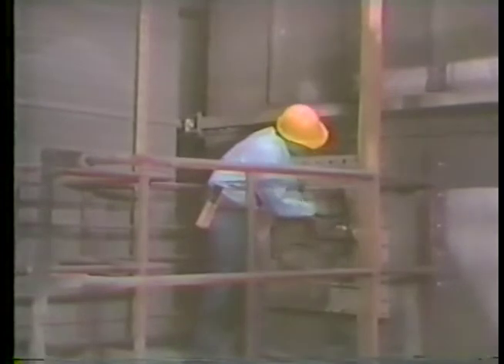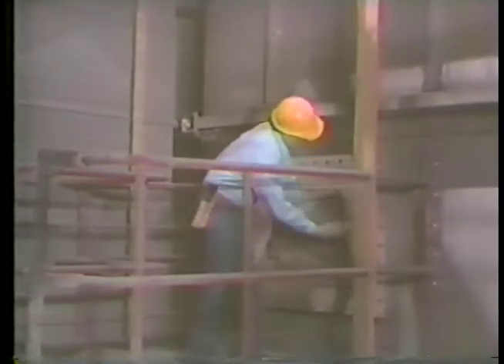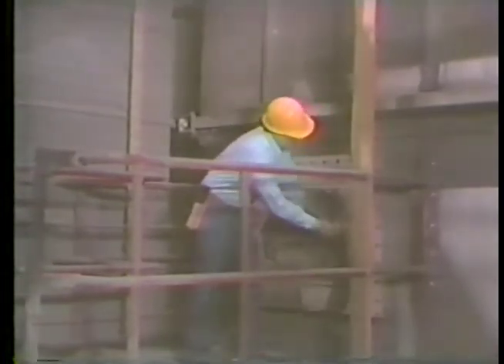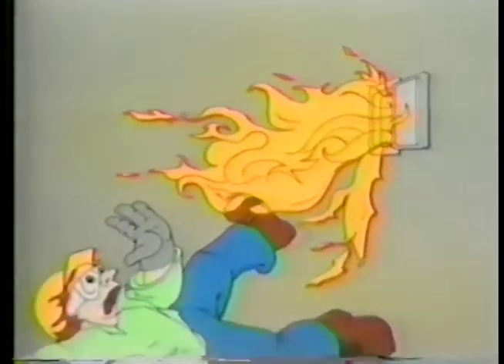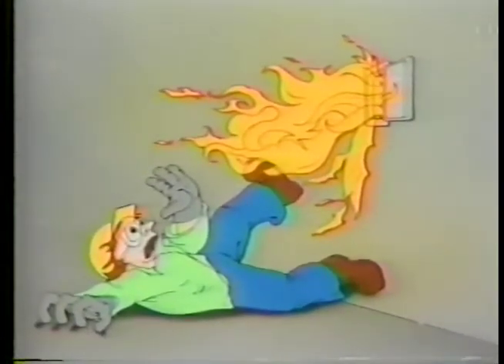One of the first checks he makes is of all openings into the boiler. Manholes, observation doors, and other openings should be closed during startup so that pressure can be established and maintained. Making sure that observation doors are closed can also be a necessary safety consideration. During startup, it's possible for a balanced draft boiler's furnace to go positive, causing flame to blow out of any opening on the furnace.